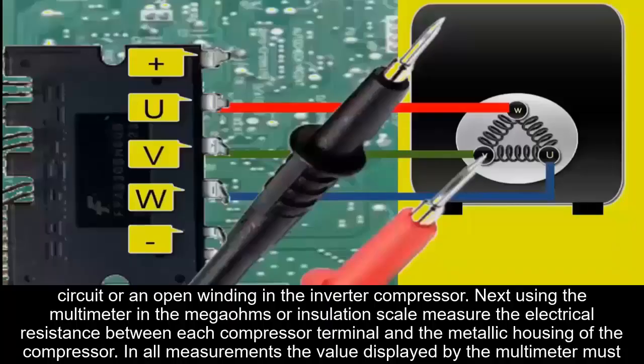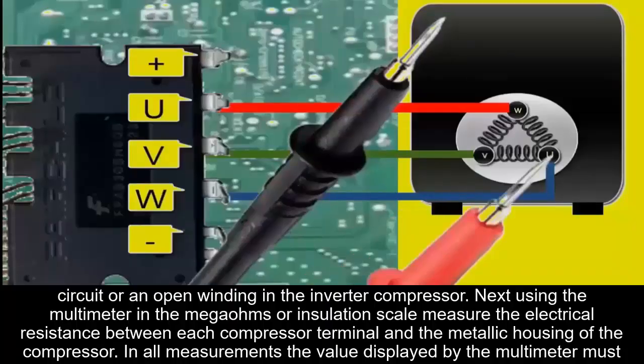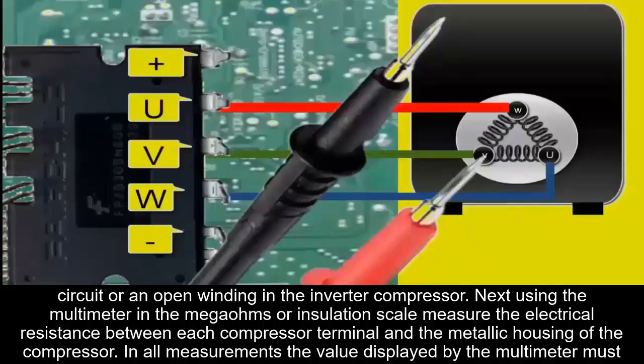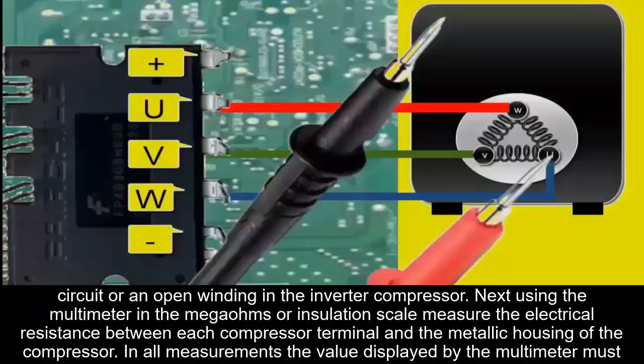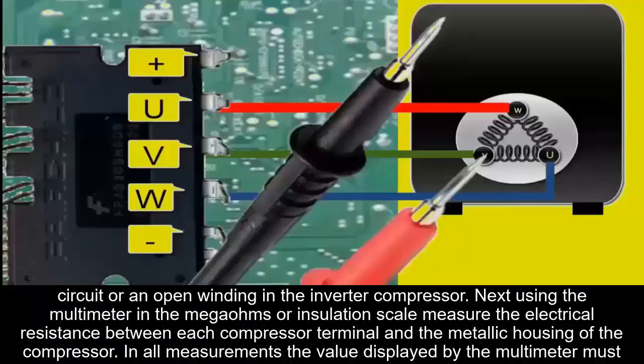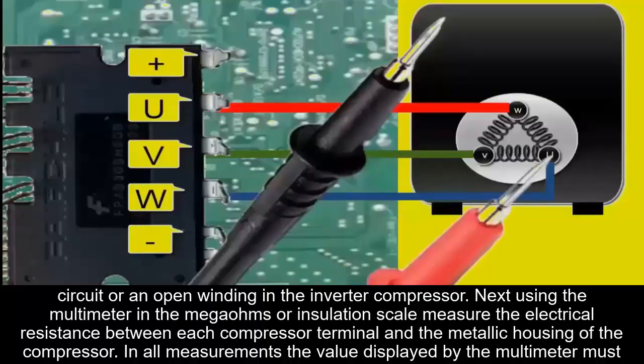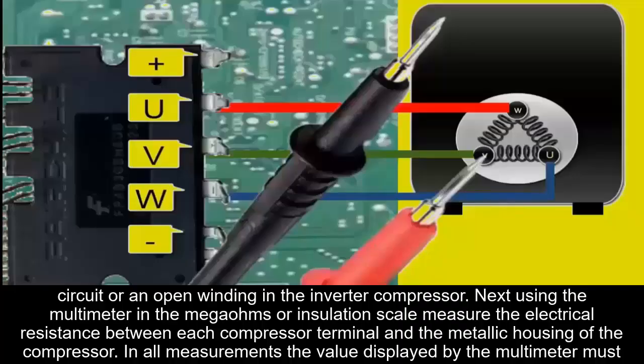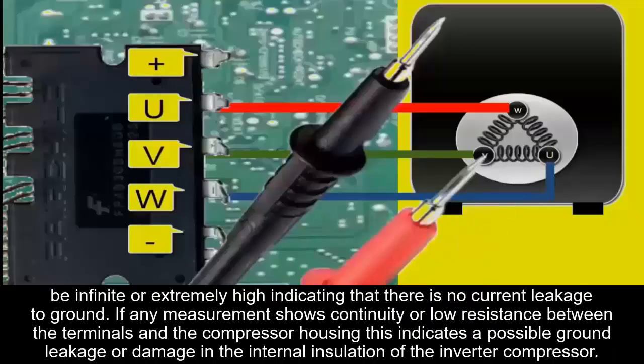Next, using the multimeter in megaohms or insulation scale, measure the electrical resistance between each compressor terminal and the metallic housing of the compressor. In all measurements, the value displayed by the multimeter must be infinite or extremely high, indicating that there is no current leakage to ground or damage in the internal insulation of the inverter compressor.